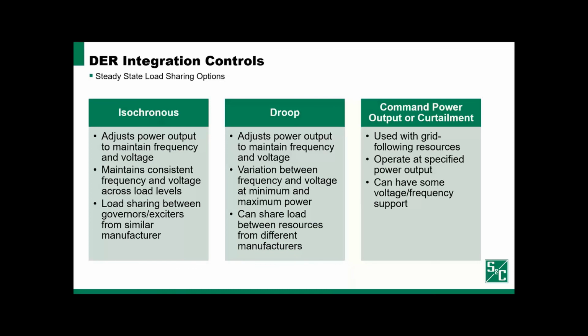If we have multiple isochronous resources, then you might ask, how do we identify which one is going to take on the additional load? And typically this is managed using load sharing algorithms that communicate rapidly between governors, exciters of resources from similar manufacturers to ensure that load is shared appropriately. When we have heterogeneous systems that utilize different types of resources or resources from different manufacturers, droop is a technique that we commonly use. And droop is very similar to isochronous, except we adjust the voltage and frequency as a function of the power output to share load between resources. And I'll expand upon that in just a moment on the next slide.